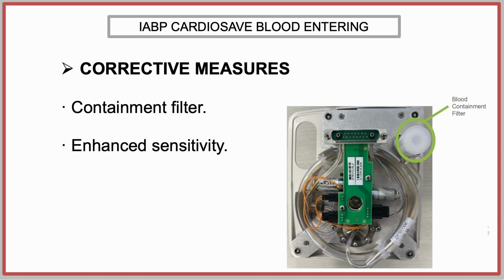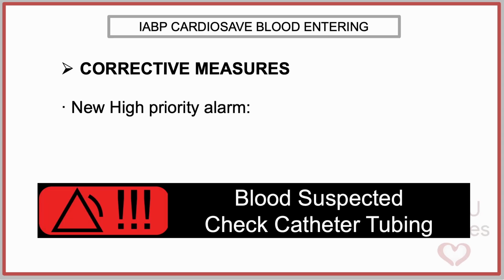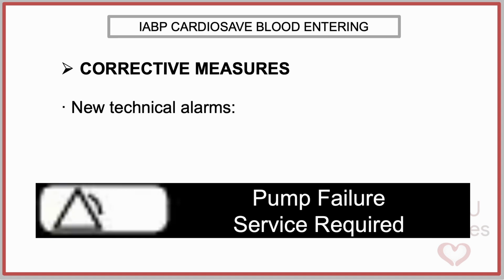In response to this event, the company has implemented a series of corrective measures. Getinge has introduced a hardware design change to the pneumatic interface module by adding a containment filter to prevent blood or fluid from reaching the printed circuit boards and electronic components. In addition, the company has deployed the following: an enhanced sensitivity for detecting pressure changes suggestive of balloon perforation, a new high priority alarm that reads, "Blood suspected, check catheter and tubing,"